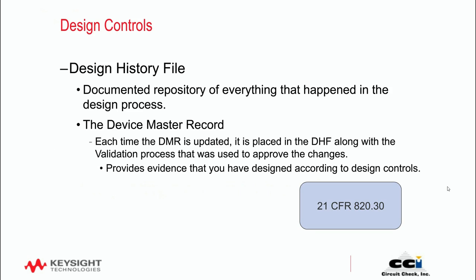Everything that you've learned up to this point is key, per the FDA, to being able to have test repeatability. As outlined in CFR 820.30, every medical device company will have a design history file that documents everything you do during the design process to ensure repeatability.